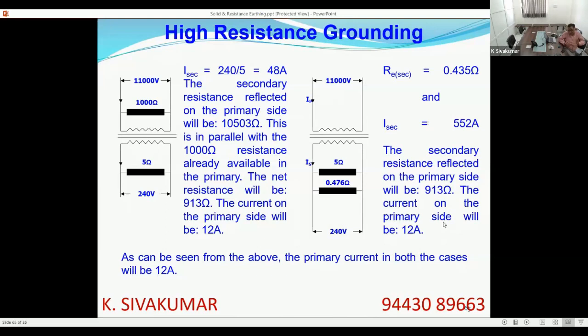Now, I am trying to explain once again. If you see the left hand portion of the slide, I have connected a 1000 ohm resistance on the HT side. I have connected a 5 ohm resistance on the LV side, maybe a load resistance, let us say. My intention is to limit the HV side current to 12 ampere, for which I have connected a 1000 ohm resistance on the HV side. Now, the LV has an integral resistance of 5 ohms, system resistance or whatever load resistance I have assumed.